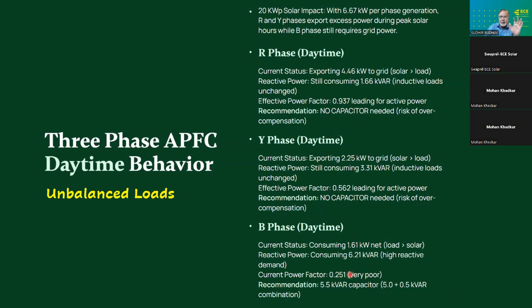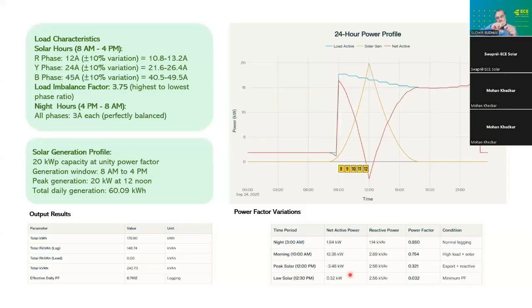It's fairly okay. So this was a steady state example of 12, 24, 45 amperes. Even if you allow a deviation of 10% plus minus per phase, and even if you take 96 time blocks at an interval of 15 minutes, that is how the energy is stored and calculated. If you plot a graph, this is actually a graph plotted on 96 intervals. The yellow line is showing the solar power injection, whereas the red line is the net power drawn from DISCOM. Here you see up to 8 o'clock or quarter to 8, the steady power demand is there. After that, it starts reducing, and till 11:30 or quarter to 12, it starts exporting.